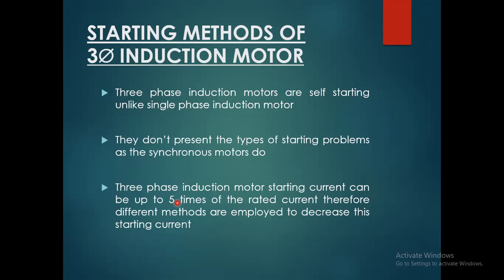32 ampere, sir. 32 ampere, 5 ampere to 32 ampere. No, it's not a feasible solution, but you can select 16 ampere. I think breakers start from 6 ampere rating. 16 ampere would be nominal, and 32 would be available there, but 16 ampere would be enough for a 5 ampere rated current of a three-phase motor. So 32 is not a good solution. 16 would be the best one. Okay, further we continue.